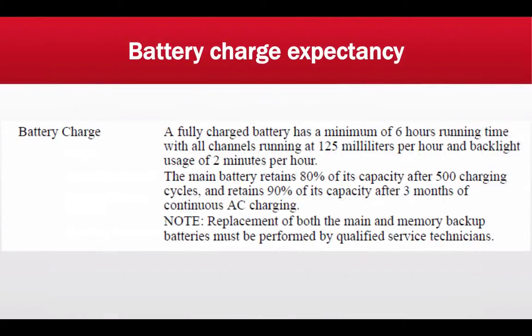This is the battery charge expectancy. So the manufacturer states a fully charged battery has a minimum of 6-hour running time, with all channels running at 125 milliliters per hour and a backlight usage of 2 minutes per hour. The main battery retains 80% of its capacity after 500 charging cycles and retains 90% of its capacity after 3 months of continuous AC charging. So I know that this is rarely the case, and you'd be lucky that you have 3 hours of usage. And truthfully, you should always have the unit charging on AC power when you conduct your transports. And the only time you should be off the AC charge is when you're moving the patients either to your ambulance or from your ambulance to the floor.